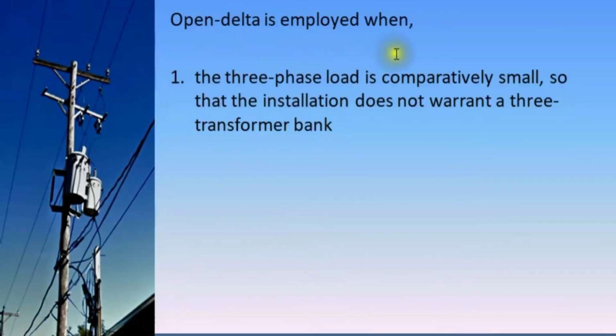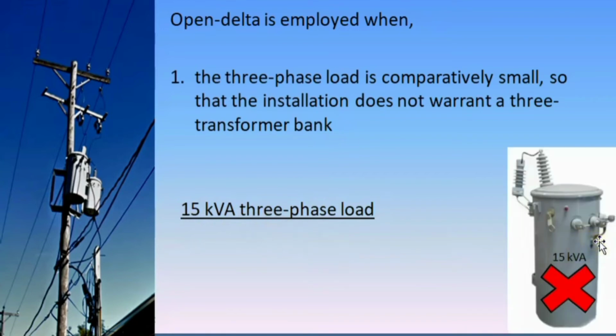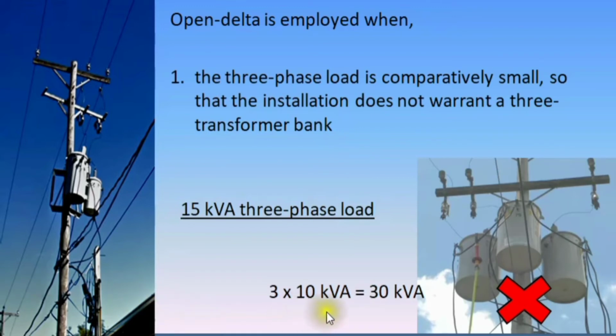Open delta is employed when, number one, the three-phase load is comparatively small so that the installation does not warrant a three-transformer bank. Example, if the computed load is 15 kVA that requires a three-phase system, obviously a 15 kVA single-phase transformer cannot be installed because the load requires a three-phase system. The lowest rating of a single-phase distribution transformer is 10 kVA. So if a closed delta transformer is used, then the capacity of the bank is 3 times 10 kVA, that's 30 kVA, which is too much for a 15 kVA load. That's why for this load, open delta system is used.